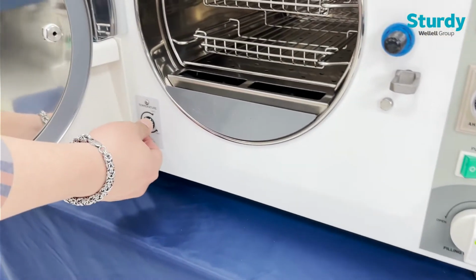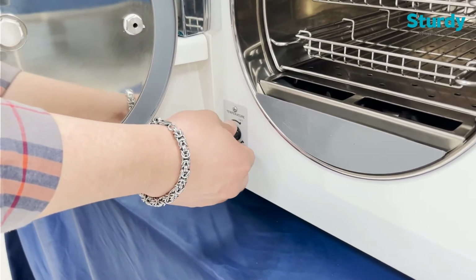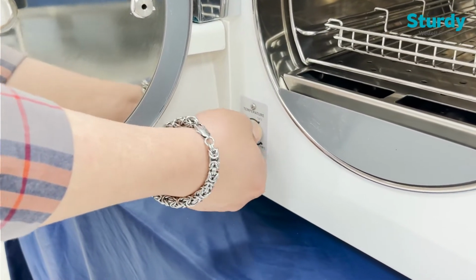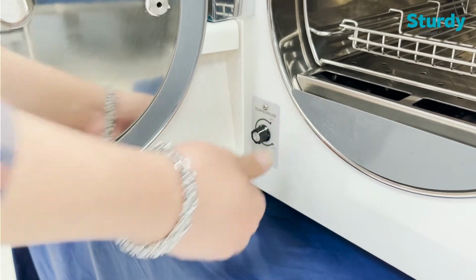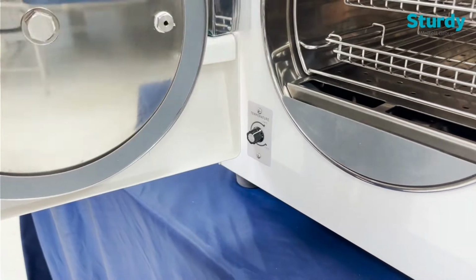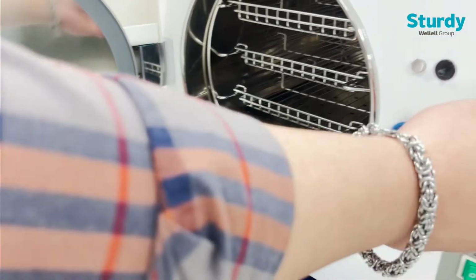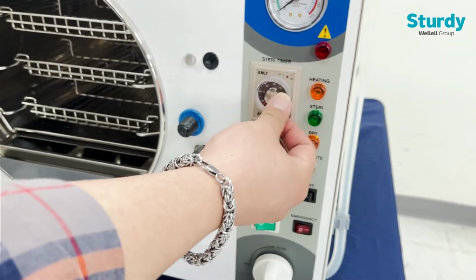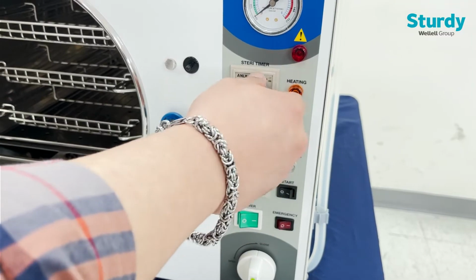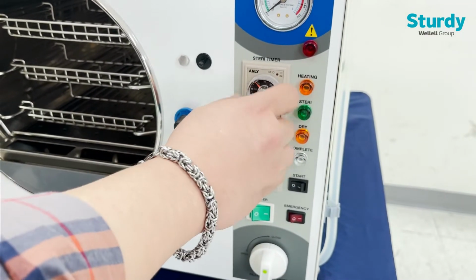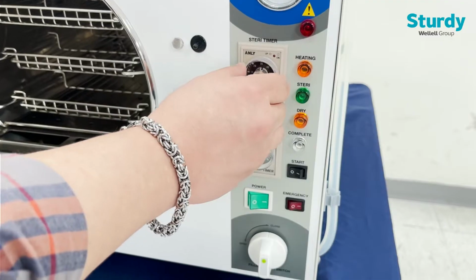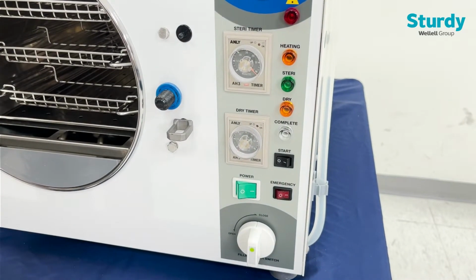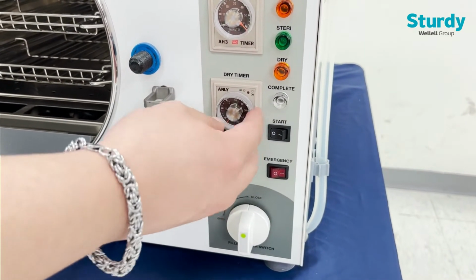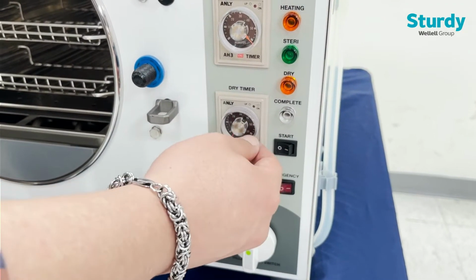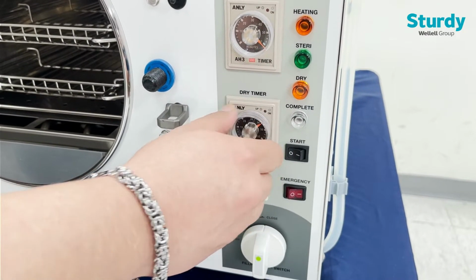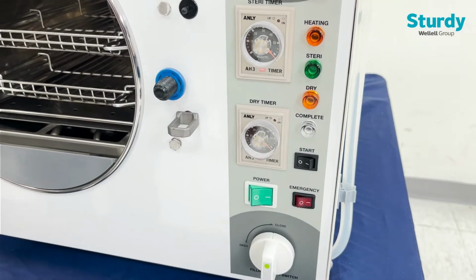Next, we set the temperature, either 121 degrees Celsius or 134 degrees Celsius. Moving on, we will set the sterilization time with the analog dial on the control panel, either to 20, 30, 40 or to the maximum 60 minutes. Next, the drying time, same as the sterilization time: from 0, 20, 40 or maximum 60 minutes.